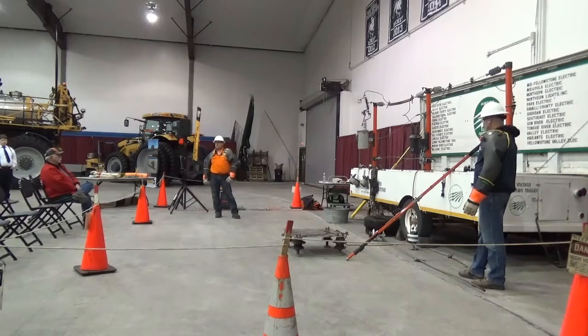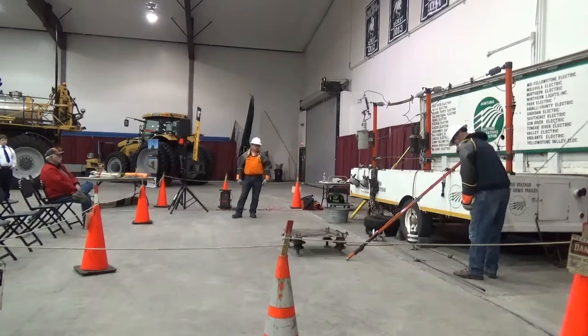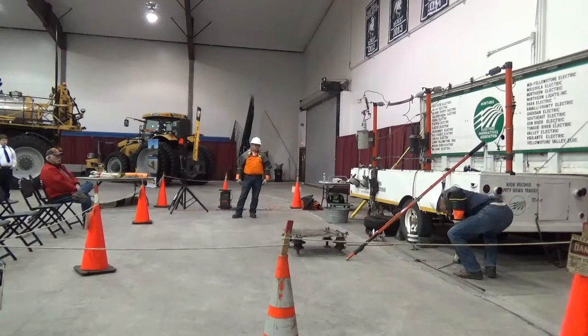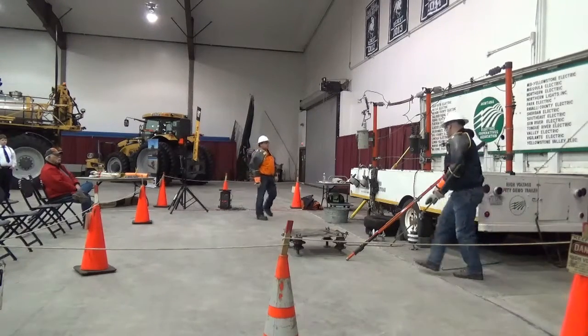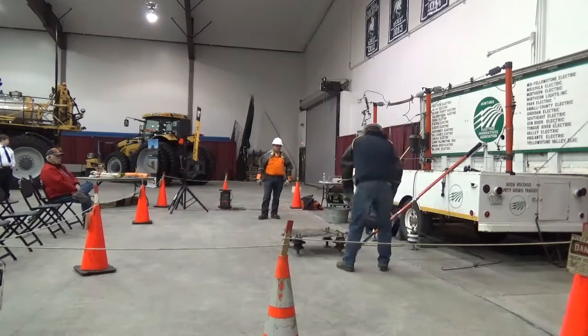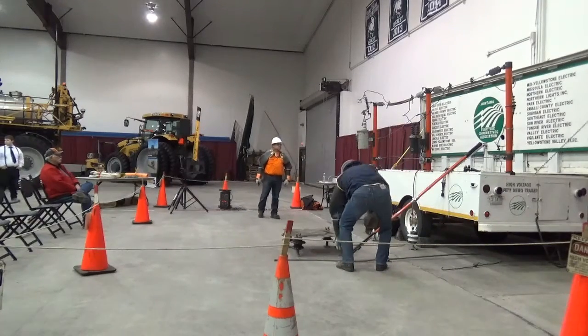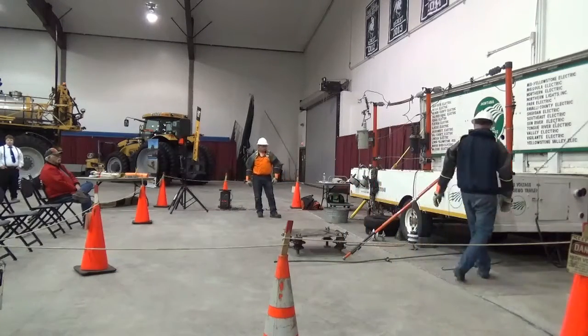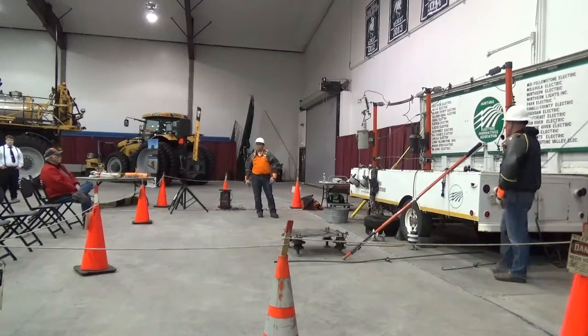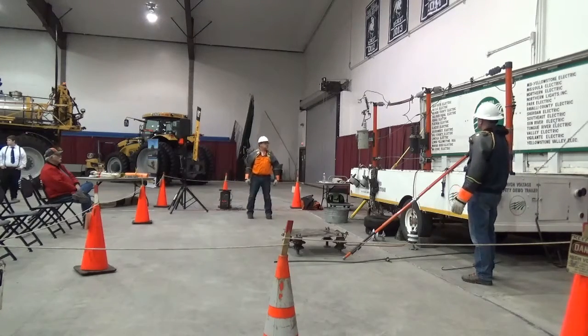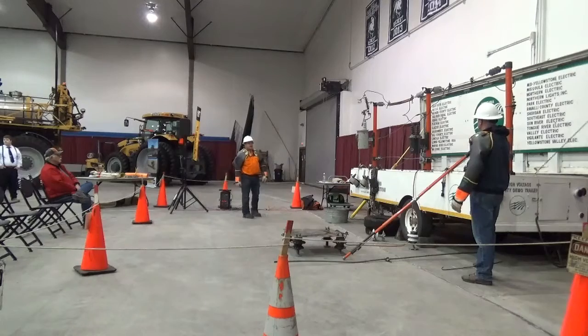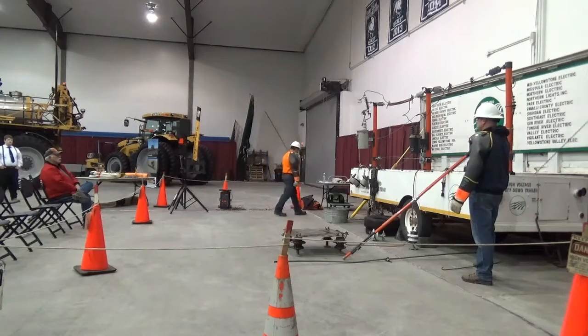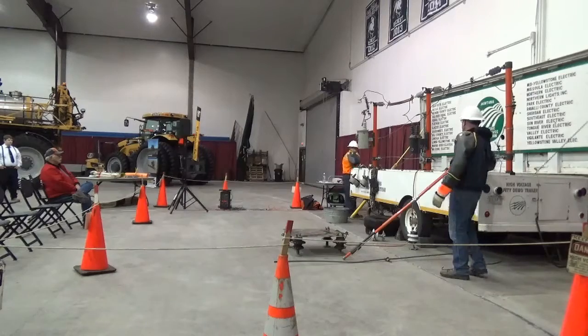Everything on our display trailer is exactly the same as you would find on a power line around your service area. Our electric is coming from the main electrical entrance in this building. By feeding 240 volts from this building into the secondary line of our transformer, our overhead line is energized at 7,200 volts. Notice the wires are not insulated. As we follow the line, we come to a fuse cutout, which protects our transformer from overloads, short circuits, and lightning. The power then flows into the second transformer where the 7,200 volts are reduced to usable household current of 120 or 240 volts, which we will use to light the bulb here on our demonstration.